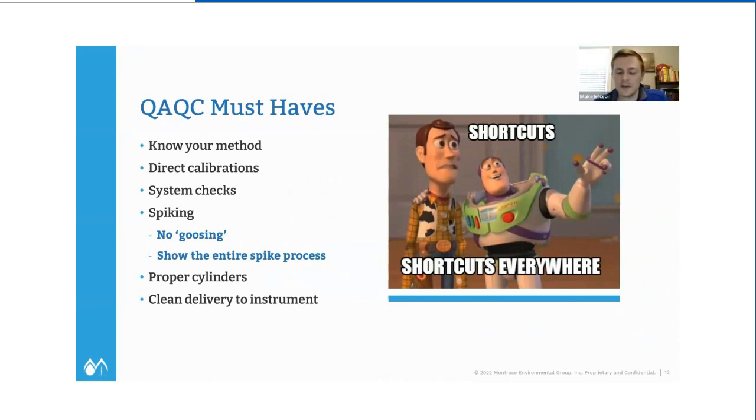So what they do is they send their sticky calibration gas, and let's just pretend it's HCl or ammonia, something like that. They send it at full blast through the system, and they essentially cut it to where they need on their dilution factor, and then they let that thing fall. Then they grab a little chunk of data that looks good, but it keeps falling, and they're not going to record that data. So it's all good, right?